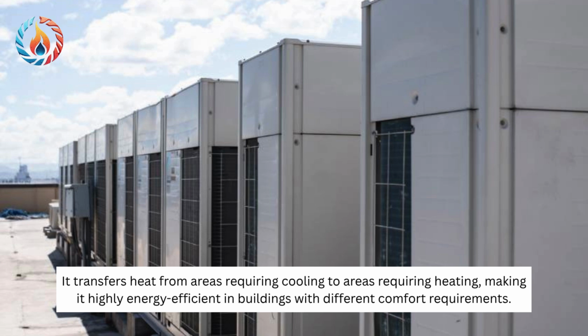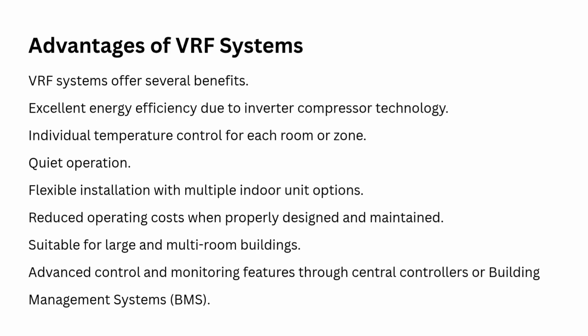Advantages of VRF systems. VRF systems offer several benefits. Excellent energy efficiency due to inverter compressor technology. Individual temperature control for each room or zone. Quiet operation. Flexible installation with multiple indoor unit options. Reduced operating costs when properly designed and maintained. Suitable for large and multi-room buildings. Advanced control and monitoring features through central controllers or building management systems, BMS.